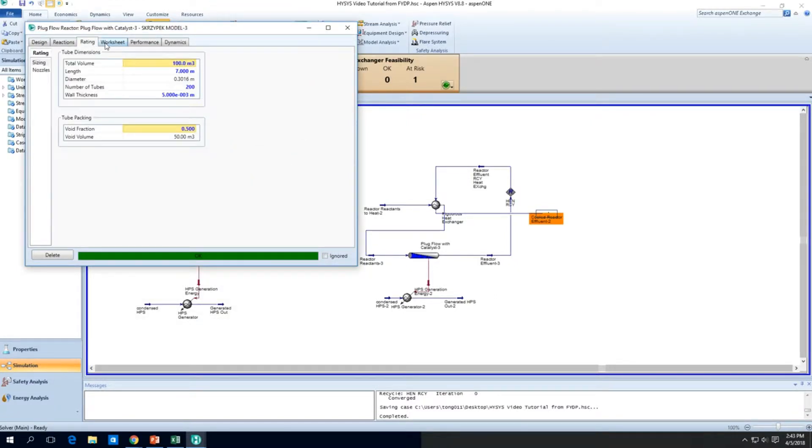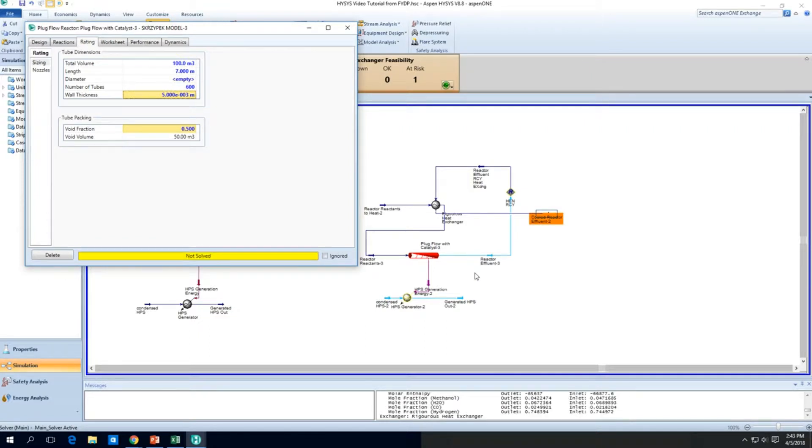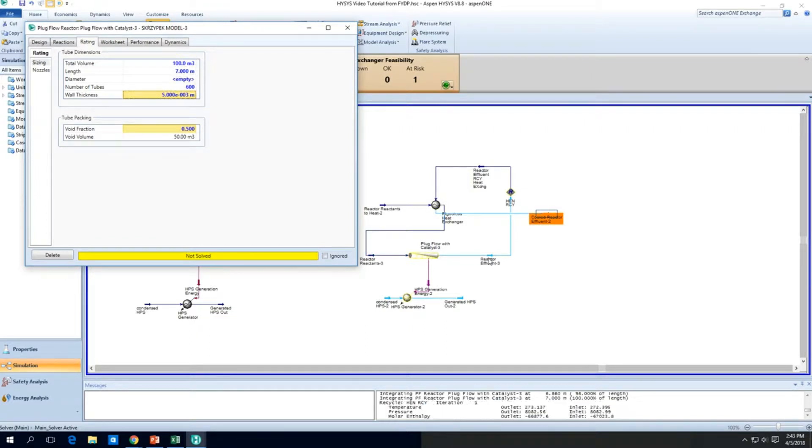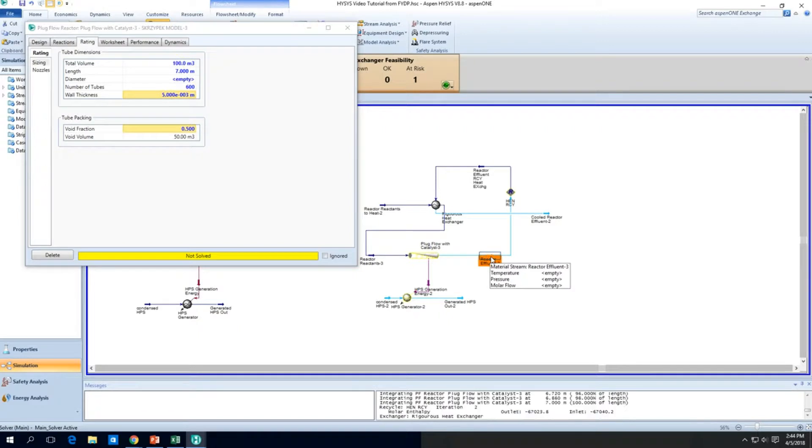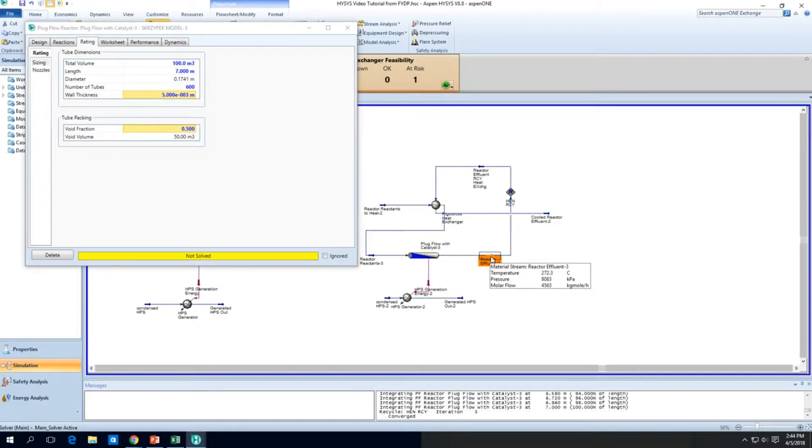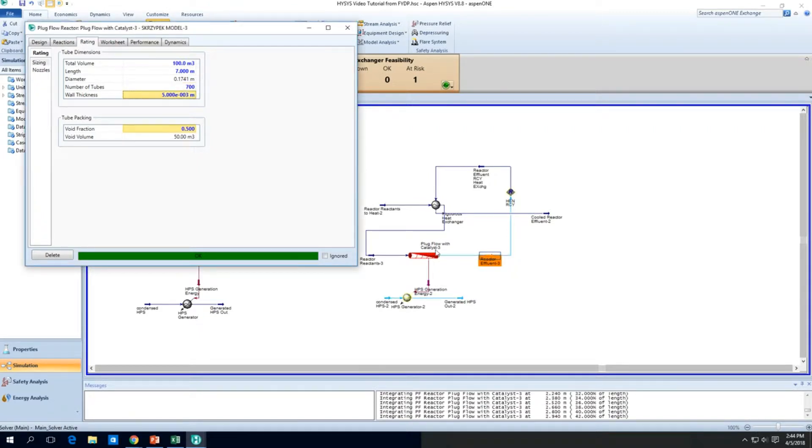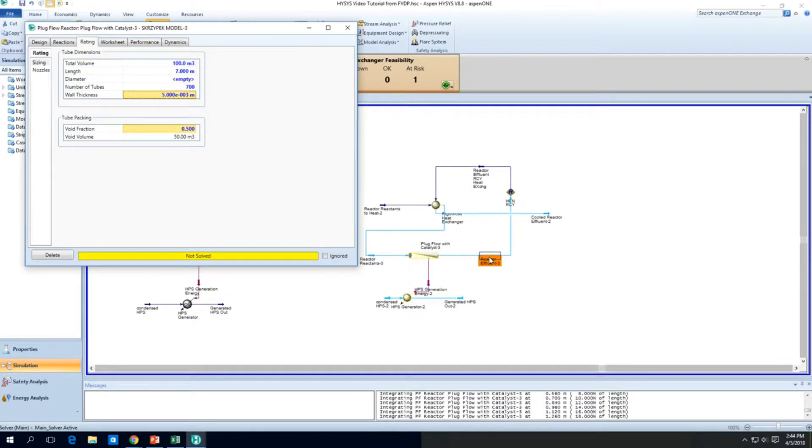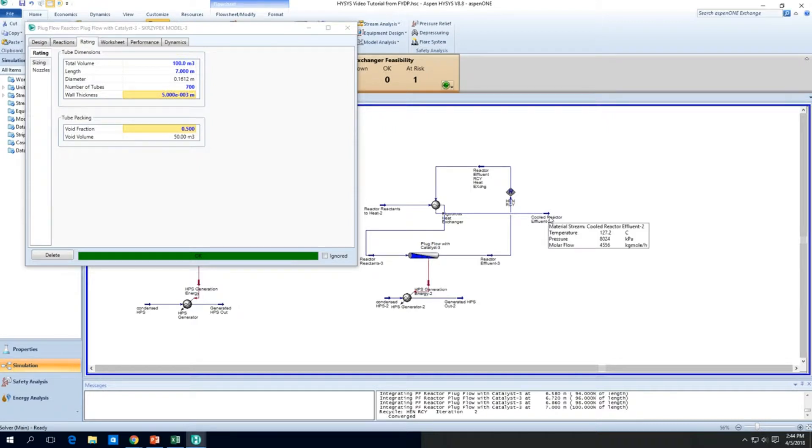So let's increase the number of tubes maybe to something like 600. That's just a kind of a guess. We want to look at this outlet temperature, we want to make sure it's around 270. So yeah, it's about 272, so let's just go a little more. 700 maybe. Okay, so 700 seems to look good. It's about 271 degrees C. It's perfect.